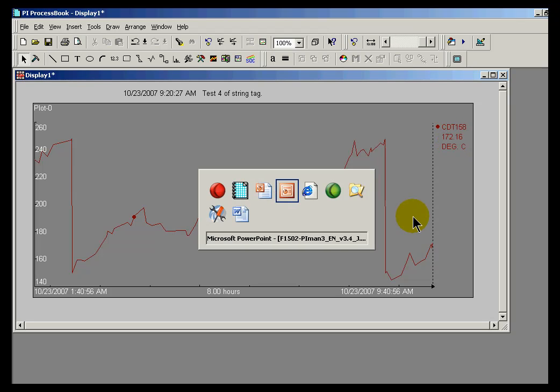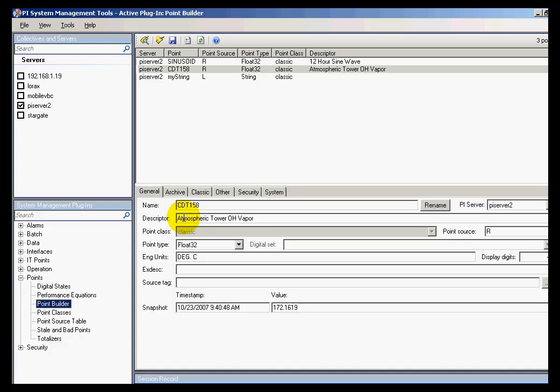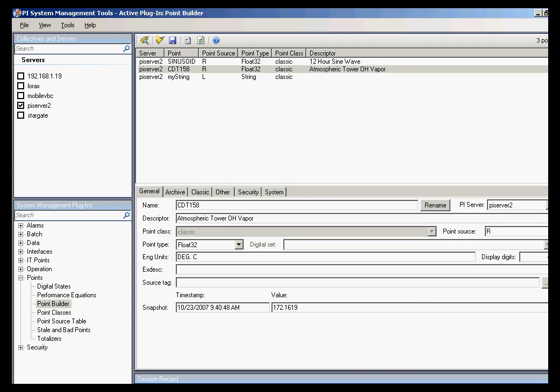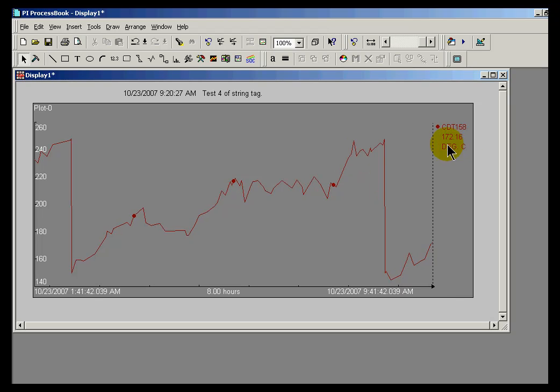Let's take a look at the definition of the tag. I'll switch over to our PI System Management Tools and look at this tag called CDT158. This is the Point Builder — just another way of editing PI tags. If we look at this, DisplayDigits is set as negative five, indicating five significant digits. Let me change that to a positive five and save the changes. Look what happens when we switch back to ProcessBook — all of a sudden we're seeing five decimal places instead of five significant digits. I'll set this back to negative five and save the changes. Within a few seconds, we see this is coming back using five significant digits. That is what DisplayDigits is controlling.